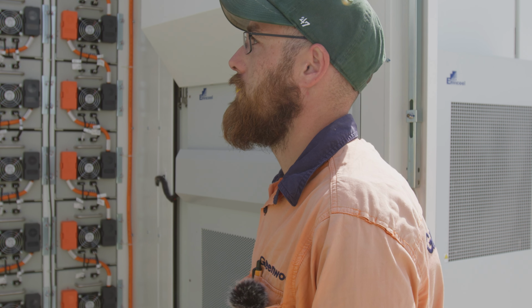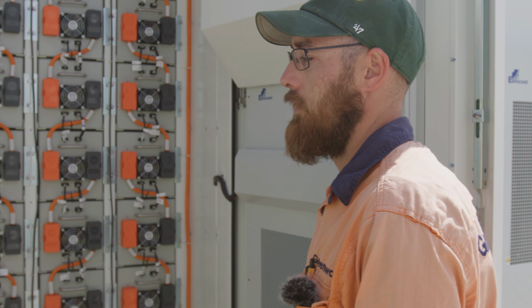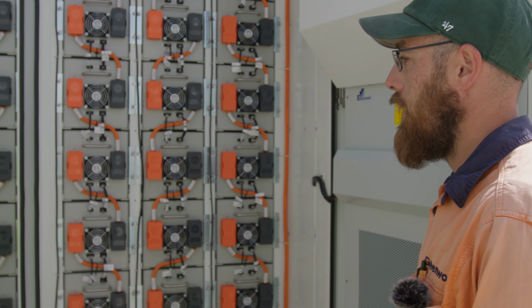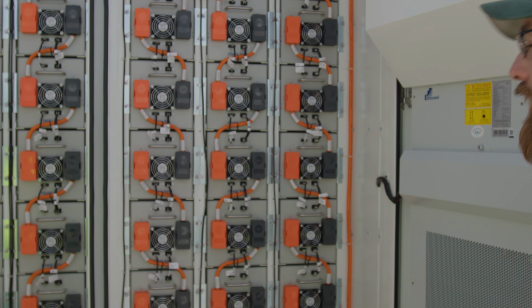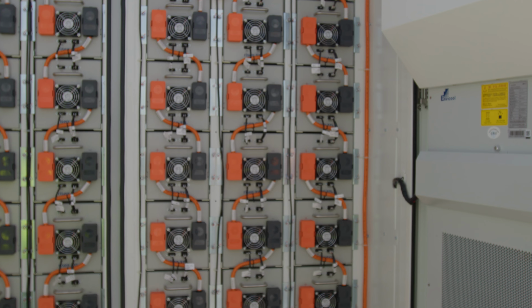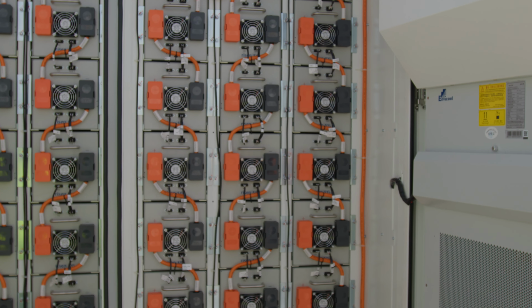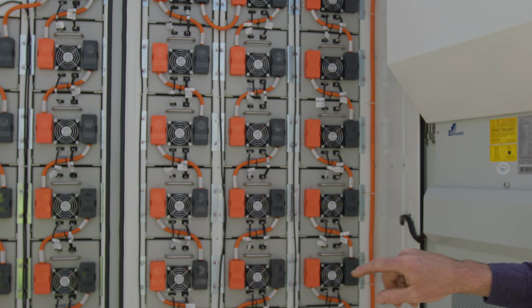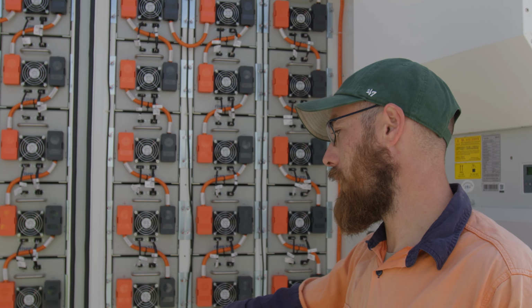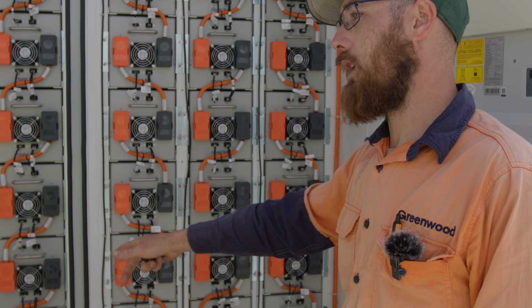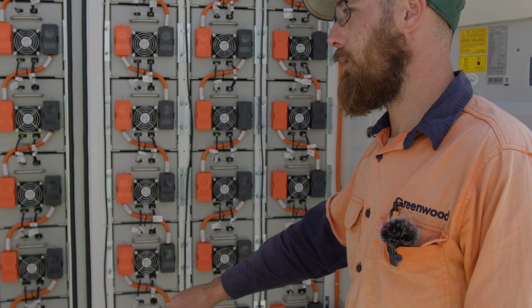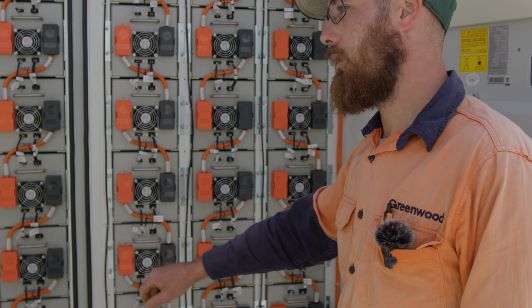And so obviously the batteries are series and paralleled? These are all just series in here. The battery cabinets themselves are run in parallel, but inside each cabinet they run series. So each battery will have the possibility of charging or discharging by 140 amps at about 40 volts.